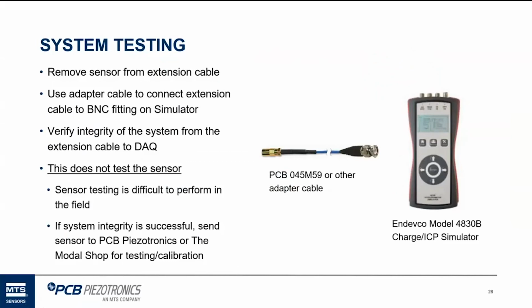For system testing, you don't really need to test the sensor, and this is my opinion. You can remove the sensor from the equation to see if it's working or not. So you remove the sensor from the extension cable, and you use an adapter cable from that extension cable, such as our 045M59 adapter, which would go right onto the extension cable. And then there's a BNC connector on the end of the sensor simulator, and you plug it into that, and you set up your parameters within the simulator, your sensitivity and your frequency, amplitudes, and you just turn it on, and you can see right away in the customer's system if it's working.